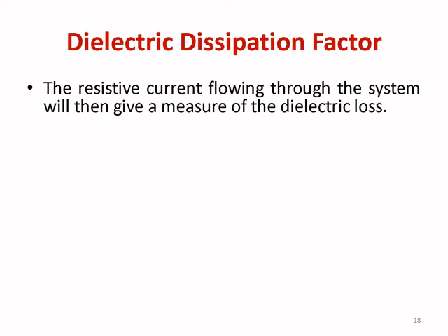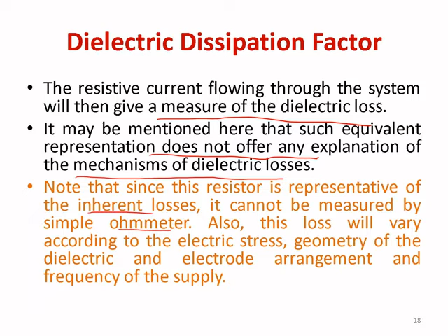And here I want to mention that equivalent representations do not offer any explanation of the mechanism of the dielectric losses. Also, you have to note that the resistor is representative of the inherent losses, but it cannot be measured by a simple ohm meter. Also, this loss will vary according to the electric stress, geometry of the dielectric, electrode arrangement, and frequency of the supply.